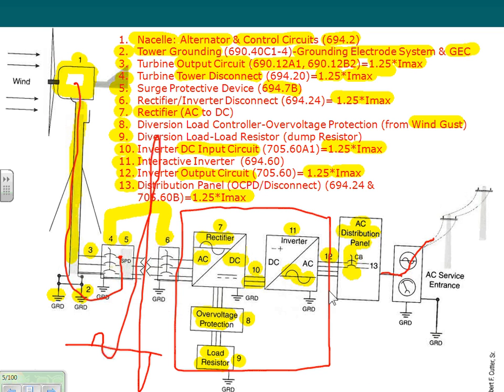Should there be a disconnect between the distribution panel and the inverter and the meter? A distribution panel and the meter. You need a disconnect to disconnect you from the grid. The one that I showed right here could be your disconnect, depending on how you connect it, that disconnects you from the grid, as well as a disconnect for the inverter.